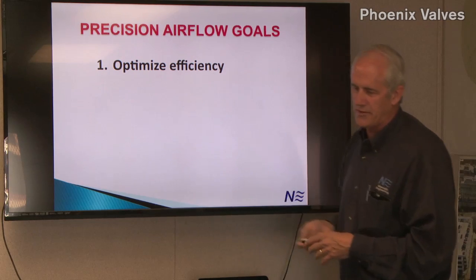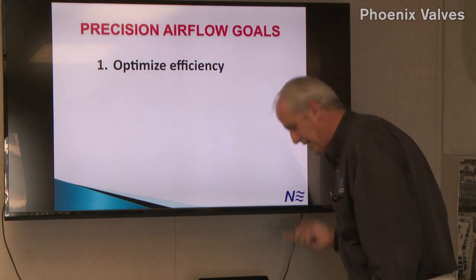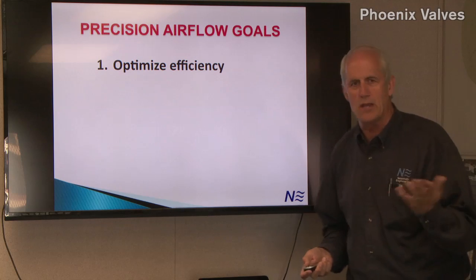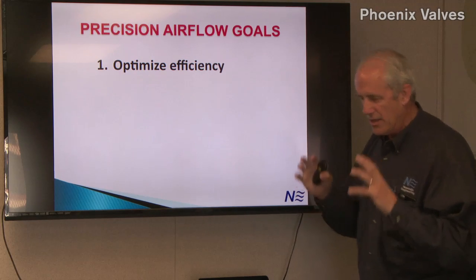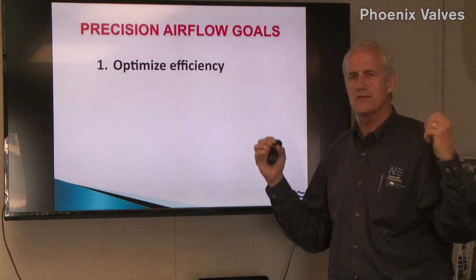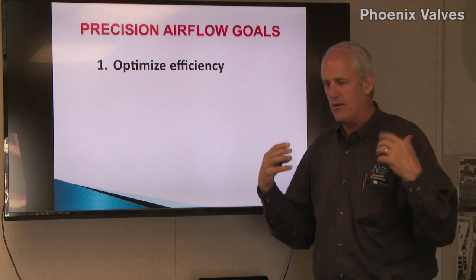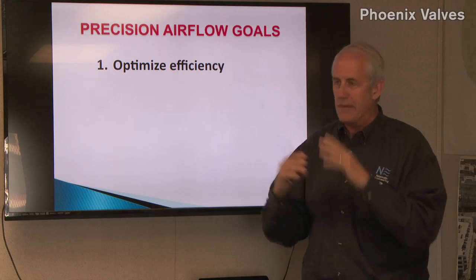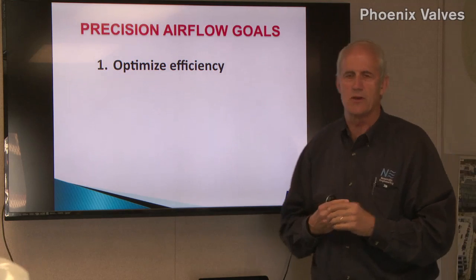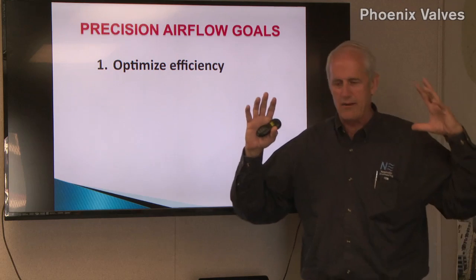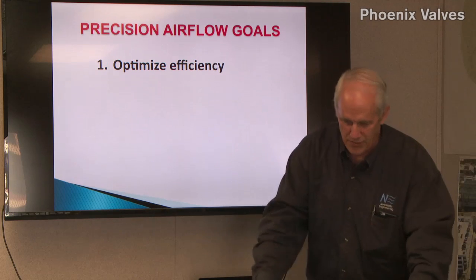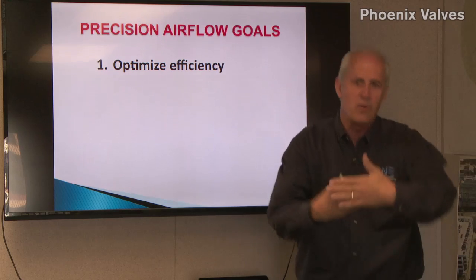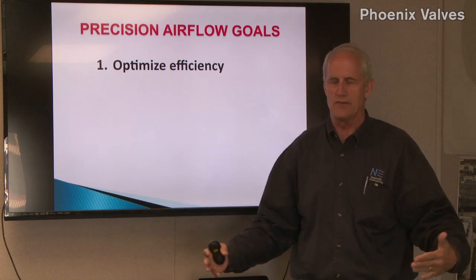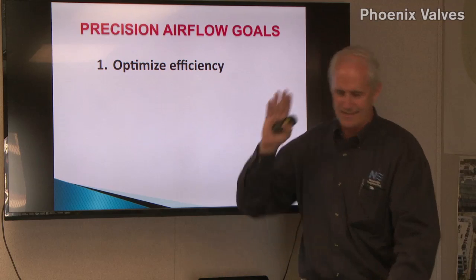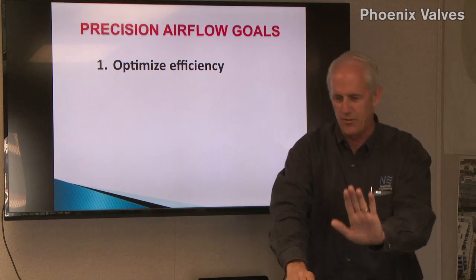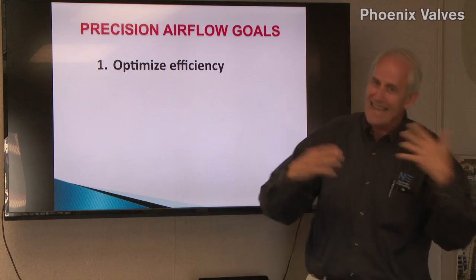So what we do is precision airflow. With precision airflow, you want to optimize efficiency. You don't want to use any more energy than you have to. You've got to have great process control. The way these buildings are designed that Phoenix is used in, they're almost inherently inefficient because process control is so crucial. That's why your air handler almost always delivers 55-degree air, and then in the lab building you reheat it at the zone level, most of it at the zone level. So you think, oh my gosh, you're cooling it so you can heat it again. Let's drive to work with the gas pedal all the way on the floor and modulate the brake pedal on the way to work. It's kind of the way the buildings run.